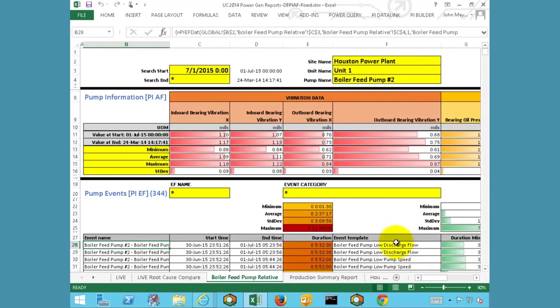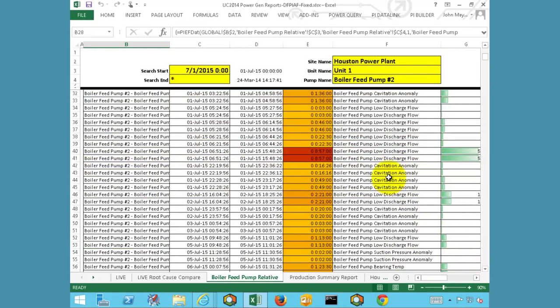Now we can see that over the past month, the boiler feed pump has had numerous events associated with it: low discharge flows, low pump speeds, cavitation anomalies, and of course the event that triggered the notification in the first place — the bearing temperature violation. Now we can sift through all of these individual events, trying to get a decent understanding of how many are occurring and in what frequency, or we can use some standard Excel features to easily summarize this information for the user.